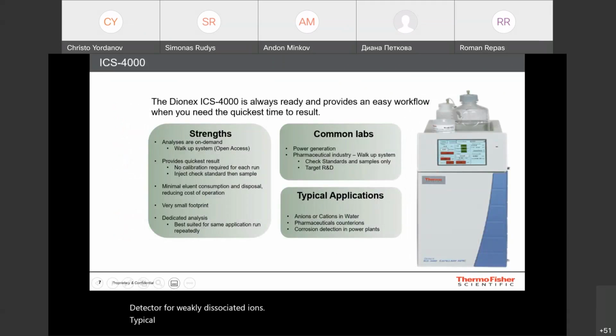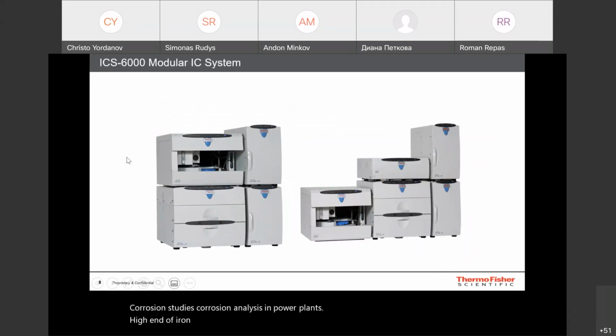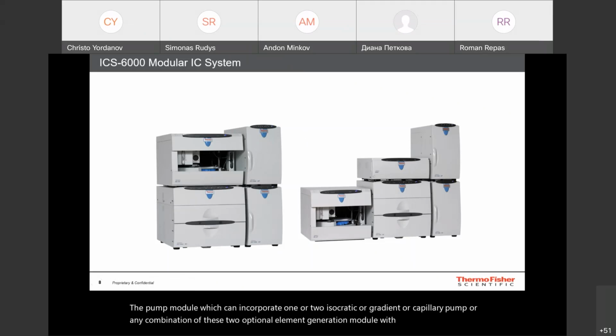Typical applications are anions, cations in mostly water samples, can be pharmaceutical samples as well, or corrosion studies, corrosion analysis in power plants. The high end of the ion chromatography product line is our modular ICS 6000 system. And this is the most flexible system for any application you can do in ion chromatography. So various modules like the pump module, which can incorporate one or two isocratic or gradient or capillary pumps, or any combination of these two. An optional eluent generation module with electronics, which can control up to two systems with eluent generator cartridges.